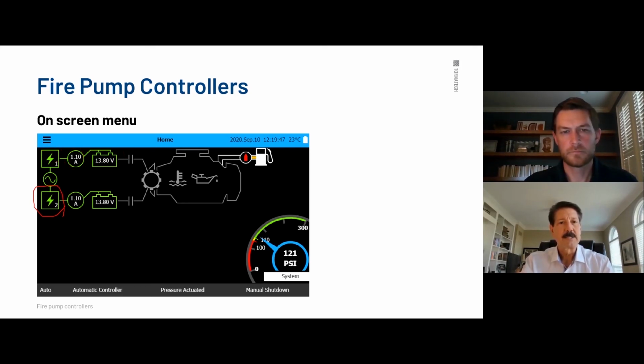And you can see green. Green is good. The starters, they're open. The engine is off, and the fuel solenoid is up in the red position or off. Everything else is the same. You see what condition is automatic, pressure actuated, manual shutdown. You see cut in, cut out, system pressure. Everything here is the same.